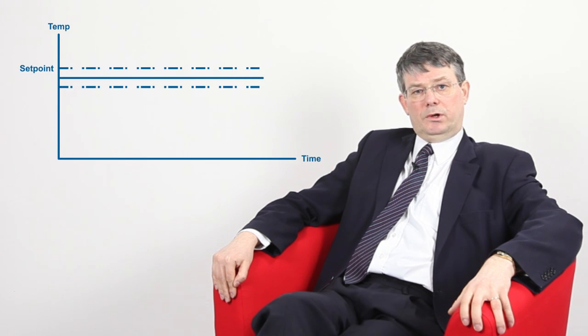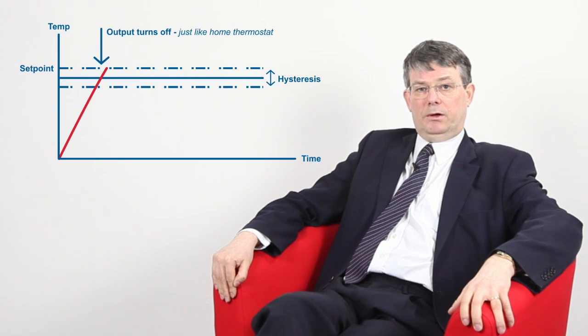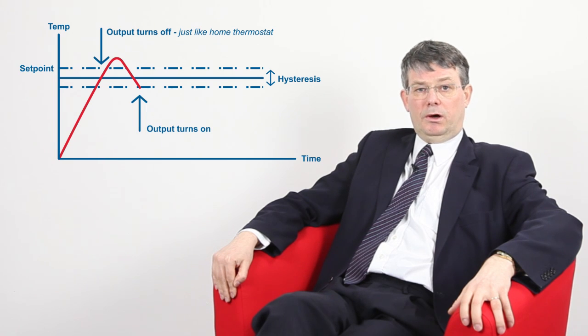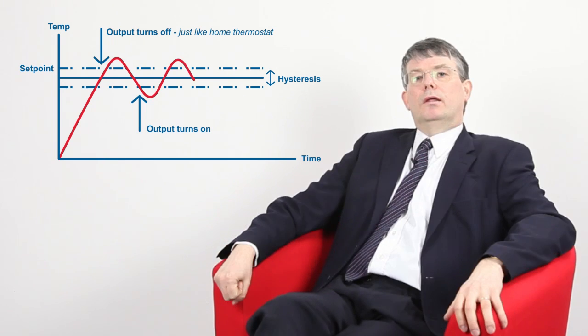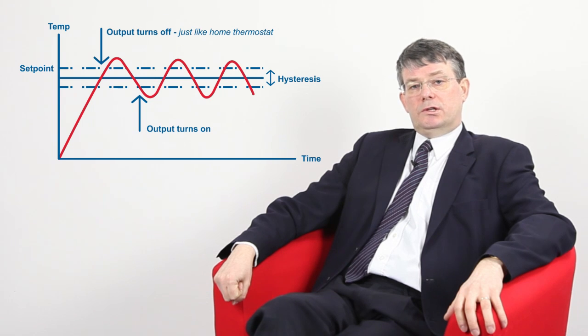With on-off control, the output will always remain on until the set point has been reached, at which point it will turn off, and will remain off until the process has fallen back below the set point, at which point it will turn back on again. This will inevitably lead to some kind of overshoot and undershoot. The amount of oscillation in the process is entirely dependent on the speed at which the process rises and falls. The user has very little control over this, except to adjust an on-off differential or hysteresis parameter if available.